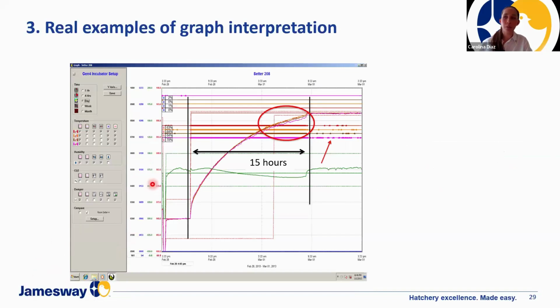Here we have another example. In this one, we have a little bit of a problem increasing the temperature at the end. It could be a pressure issue, or on some controls we can have water and heating elements activated during the warm-up. For example, if there's a set point we can adjust to have both systems running until a certain time and then keep heating just with heating elements, this could be one of those cases where at the end it was heating just by heating elements instead of heating and water. So it took a little bit longer to warm up.